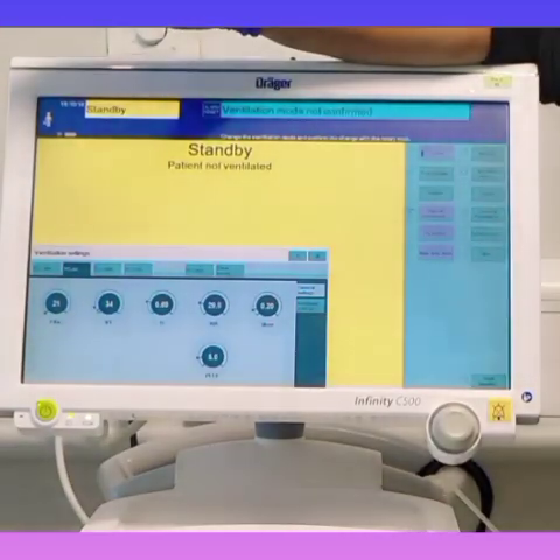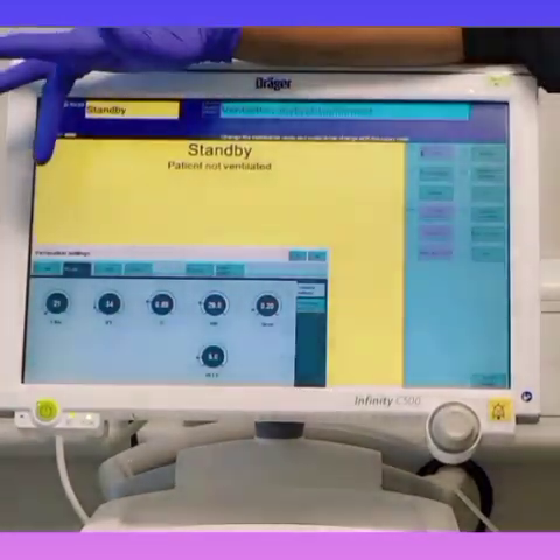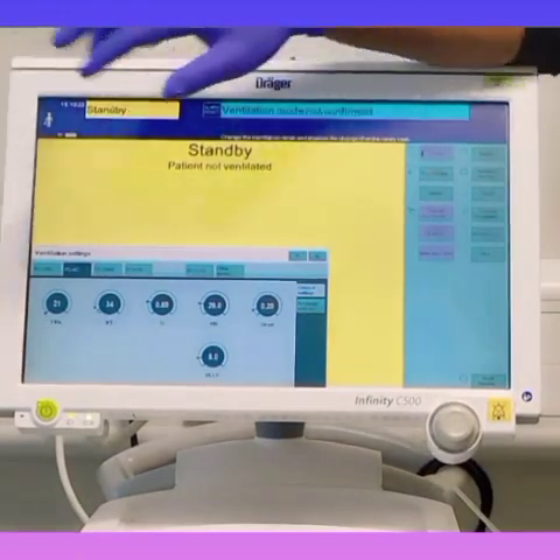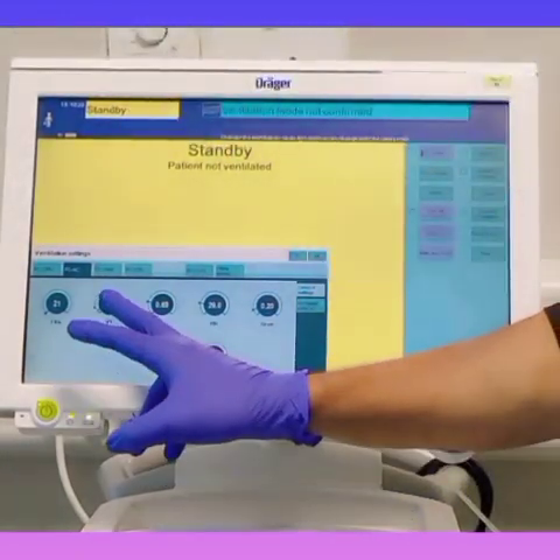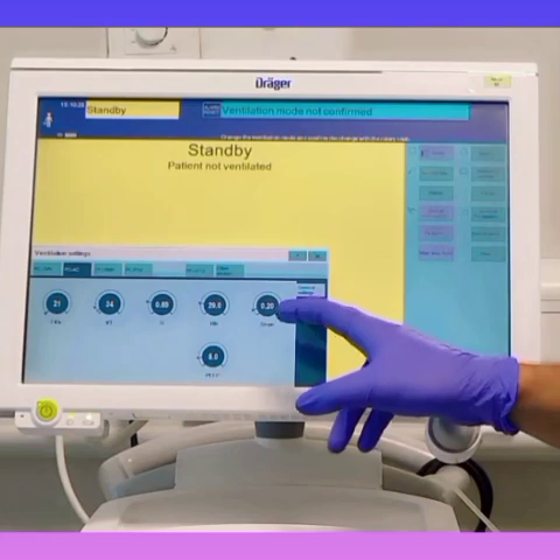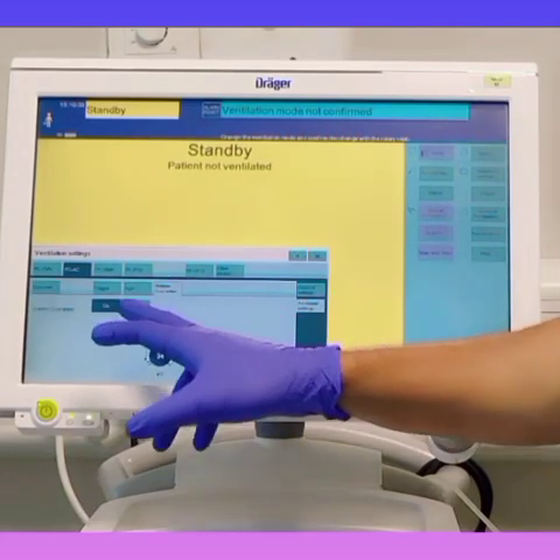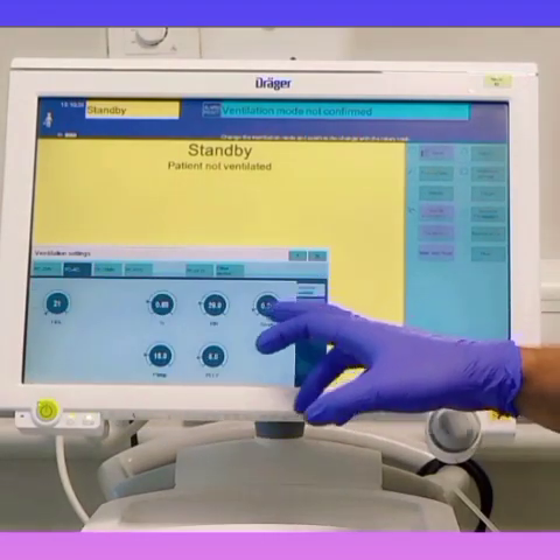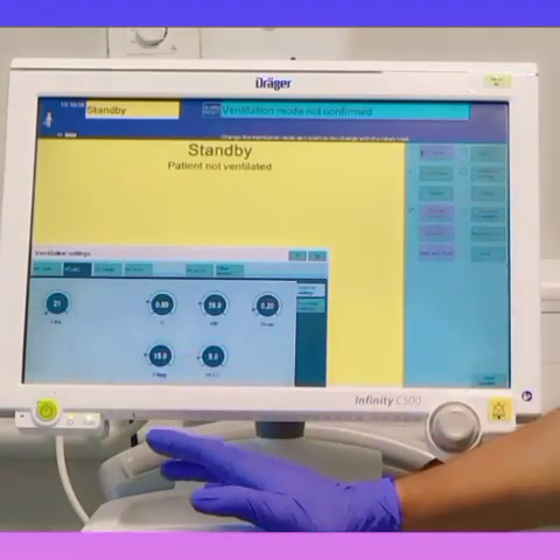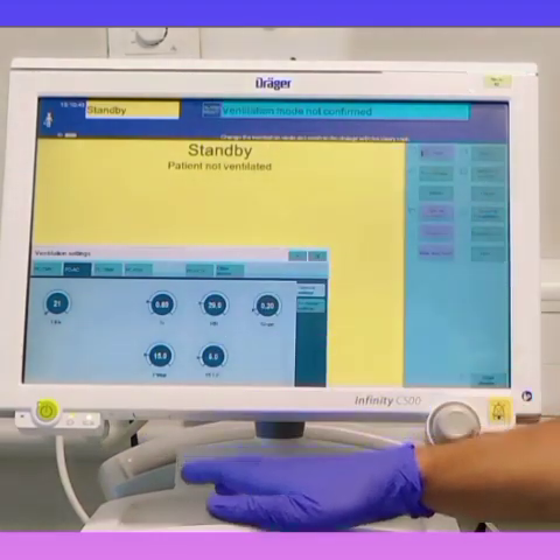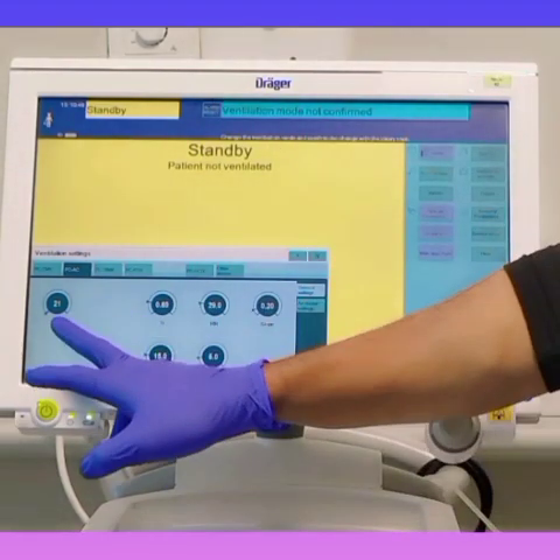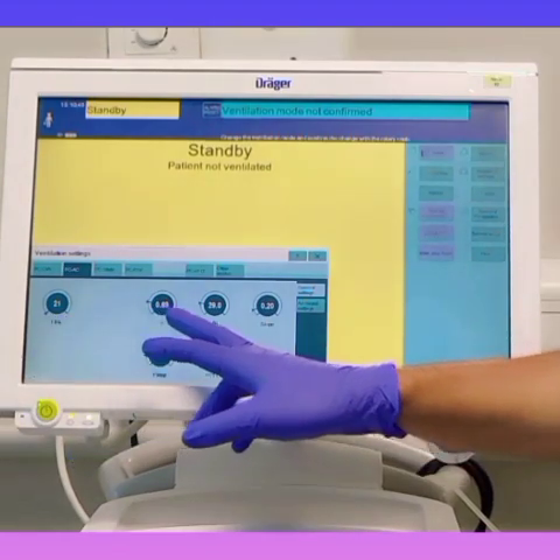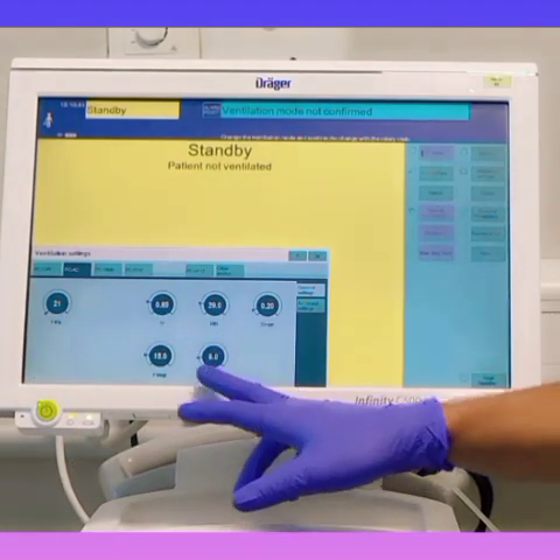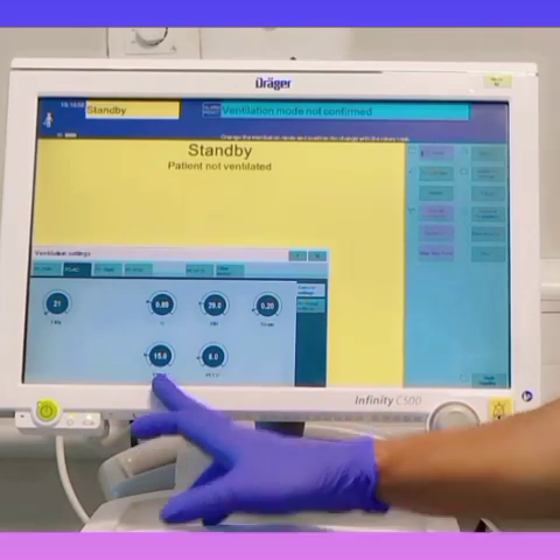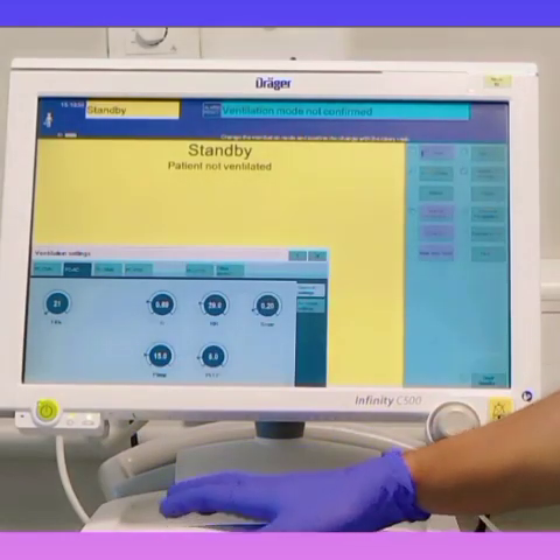So for control mode, we have to go to the ACPC. For pressure control, you can see here we have tidal volume. First of all, you have to go to the additional settings, go to the volume guarantee and turn it off. Now you go back to the general settings. You can see here there is no tidal volume. Now this mode is purely controlled by pressure. Here we have the FiO2, inspiratory time, respiratory rate, PEEP and inspiratory pressure. So this mode will be your pressure control mode.